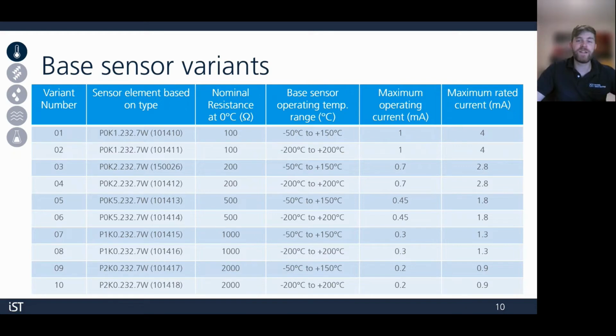I mentioned some accuracy classes before. In this case, all of these chips are Class B according to the IEC 60751 norm for thin film platinum elements. For enhanced accuracy, we can perform a measurement service on request and provide individual curve coefficients for each sensor.